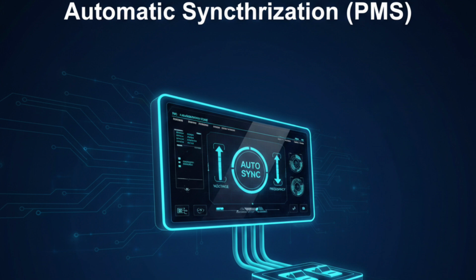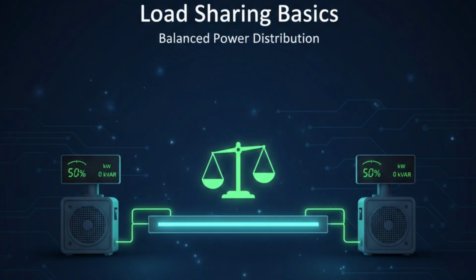Load sharing basics. Once synchronization is complete, both generators operate in parallel. Now the next important thing is load sharing. Load sharing means distributing electrical load equally between generators. There are two types of load. Active power, measured in kilowatts, or kW. Reactive power, measured in kVAR. Active power depends on engine fuel input. Reactive power depends on generator excitation. If load is not shared properly, one generator may overload. Other generator may run underloaded. Reverse power trip may occur. Proper load sharing ensures efficient fuel usage, balanced operation, long equipment life, system stability. Parallel operation must always maintain balance.